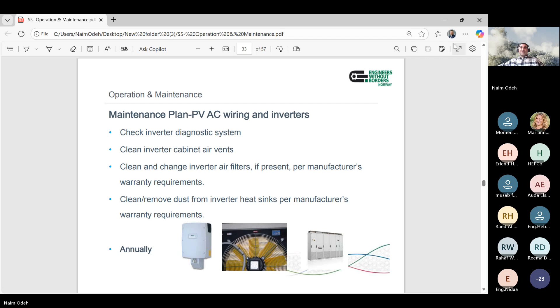Okay, same thing for wires and cables. You need to check the inverters, if everything is fine, the ventilation system is okay, the fans of the inverters are okay. Sometimes you just need to replace the filters if they are not clean. Even if you don't replace them directly, sometimes you clean them multiple times before you just replace them. Check the dust and other stuff just to make sure everything is fine.